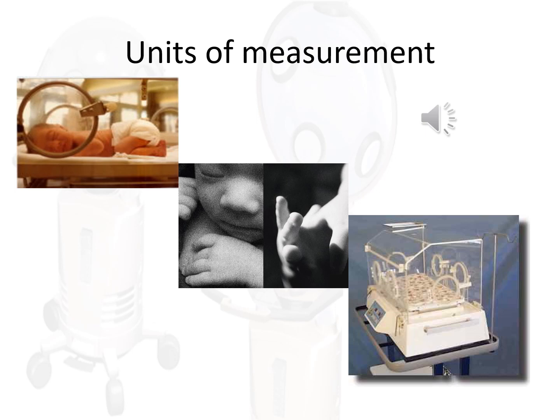In the infant incubator, we measure air temperature between 32 and 38 degrees Celsius, baby skin temperature between 34 and 36 degrees Celsius, total gas intake of 35 liters per minute, and relative humidity of 50 to 70%.